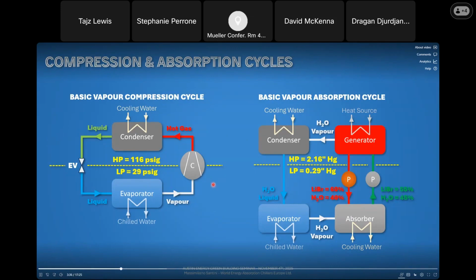To do that, compression chillers use a compressor using electricity to do this work, while the absorption cycle, as you can see, has two additional heat exchangers, the absorber and the generator. So after the refrigerant vapor evaporates in the evaporator, this is absorbed by a solution of 60% lithium bromide, which is a salt, so is hygroscopic and at certain concentration can absorb water vapor. After absorbing the refrigerant, the solution gets diluted from 60% lithium bromide to 55%.